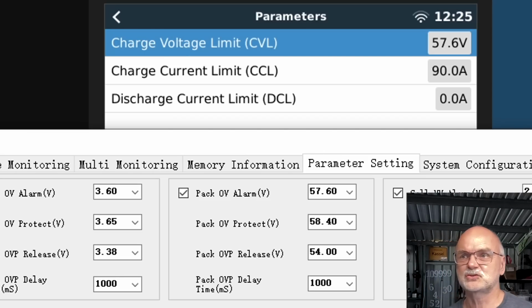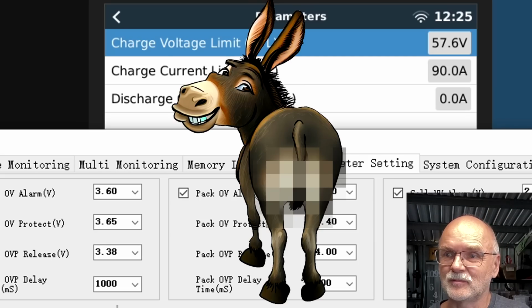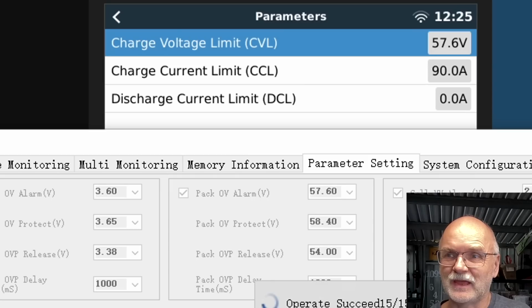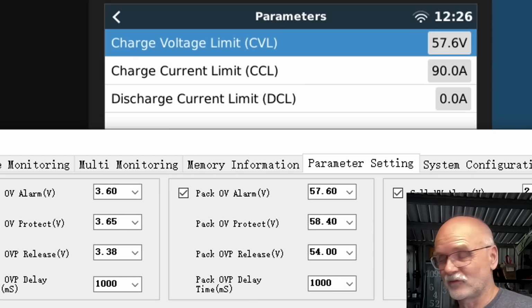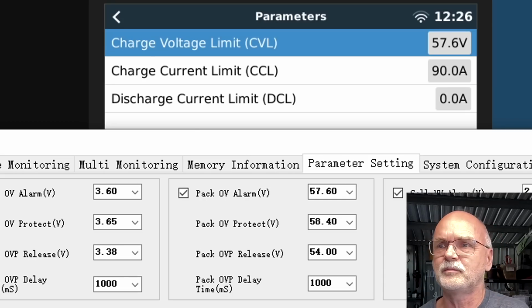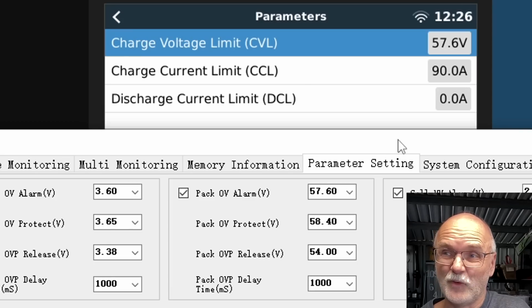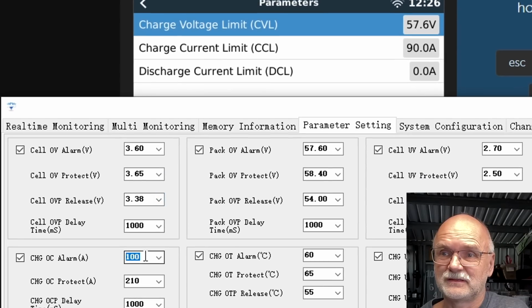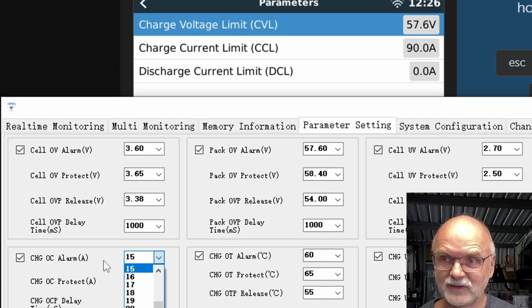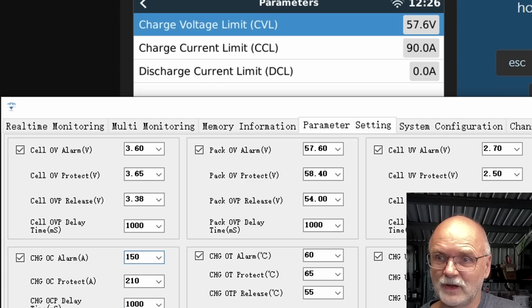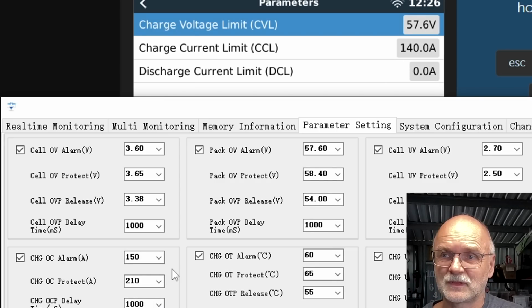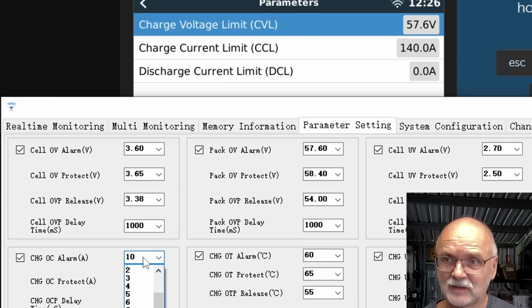Okay, protocol has changed to Victron. Communication sucks completely. Let me try the Pylon Tech protocol, because this usually works with Victron as well. Okay, it now sits on Pylon Tech. Discharge limit is still 0. It would tell the inverter now, don't discharge from this battery. And nothing changes here. Does this actually change at all? 150 amps. And right. Yeah, so it communicates with the servo, obviously, but not with the discharge parameters.